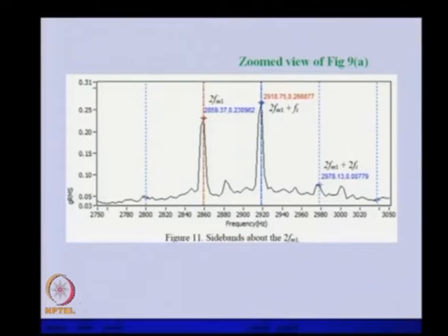This is another zoom view of the same figure. In this you can see that additionally we have FM1, shown here in the higher range, and there is a sideband. The sideband is more predominant than the actual first tooth missing frequency. Here it has been modulated. Even this is the higher harmonic of the tooth missing frequency, the second harmonic of the tooth missing frequency, and the sideband of that. Here also there are higher sidebands, at twice the speed of the shaft.